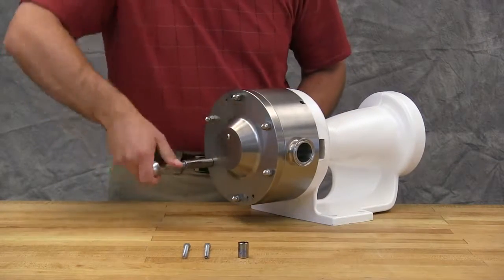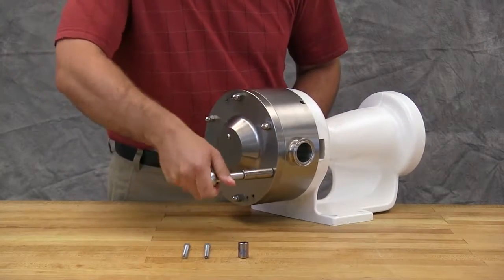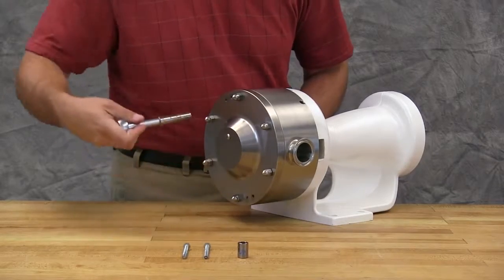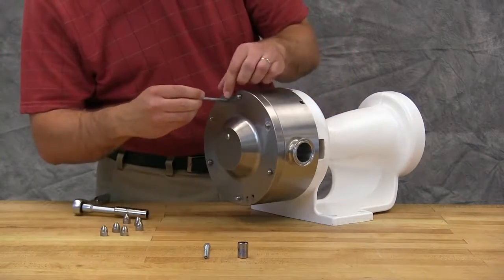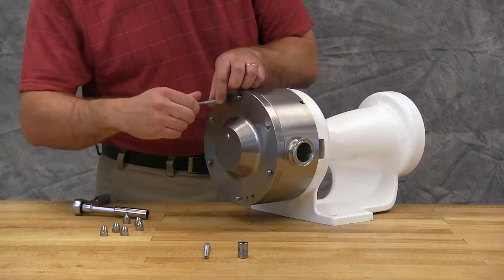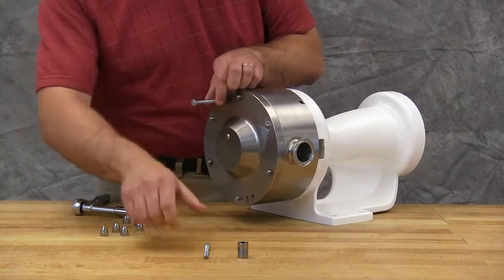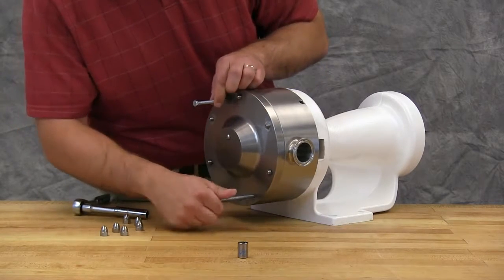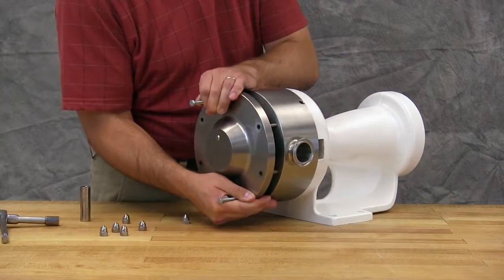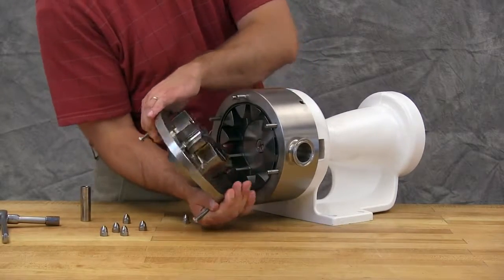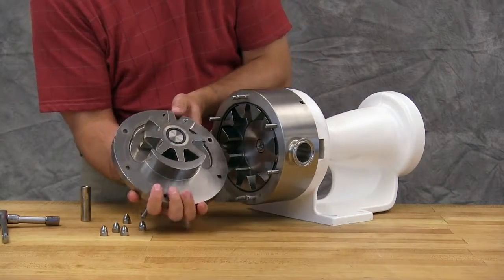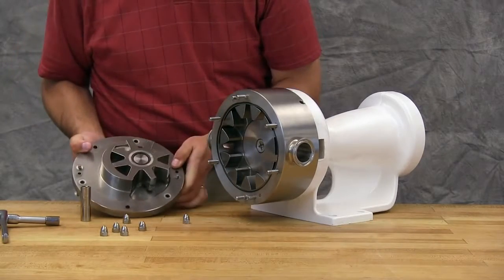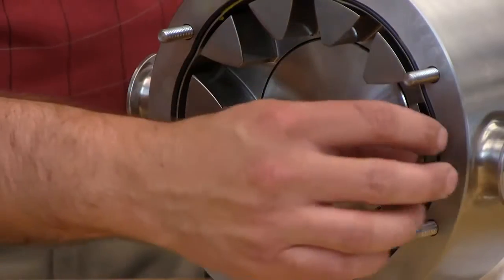If the pump has a jacketed head plate, remove the jacketed head plate and O-ring. Use jack screws to back the head away from the casing. Remove the head by tilting it backward to prevent the idler from falling off the idler pin. Remove the head O-ring.